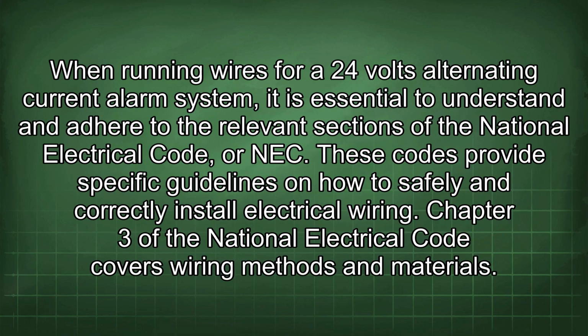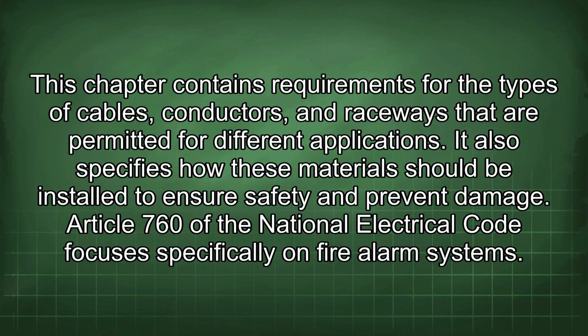When running wires for a 24 volts alternating current alarm system, it is essential to understand and adhere to the relevant sections of the National Electrical Code, or NEC. These codes provide specific guidelines on how to safely and correctly install electrical wiring. Chapter 3 of the National Electrical Code covers wiring methods and materials. This chapter contains requirements for the types of cables, conductors, and raceways that are permitted for different applications. It also specifies how these materials should be installed to ensure safety and prevent damage.